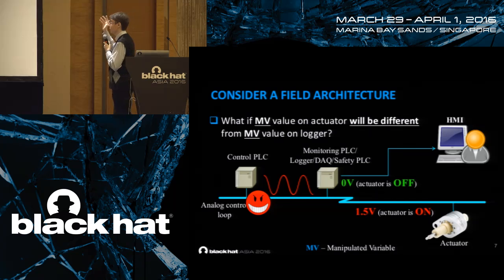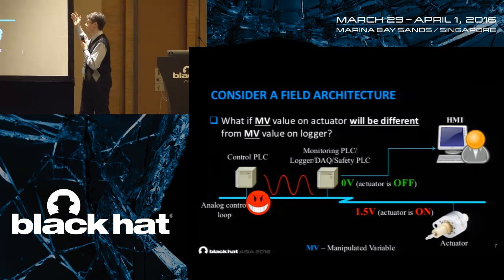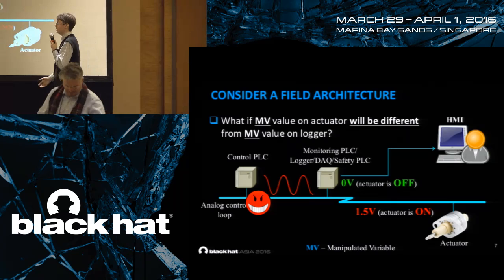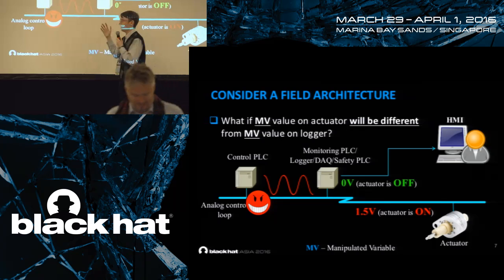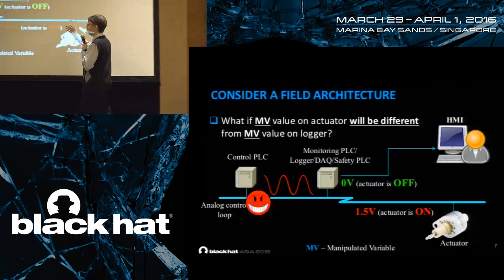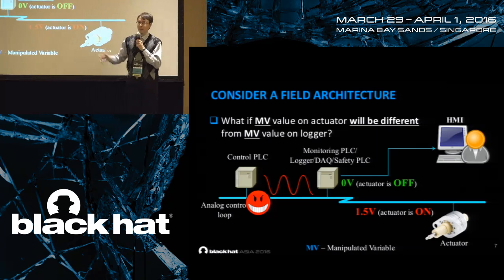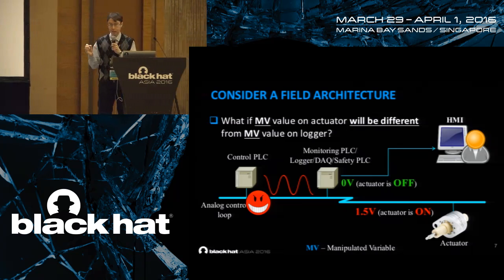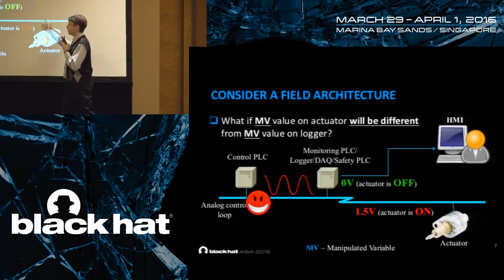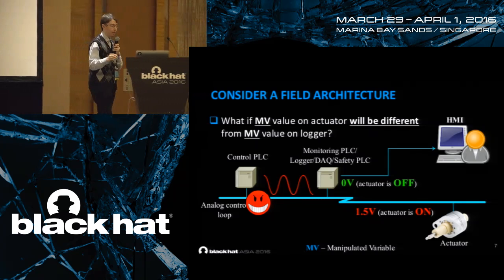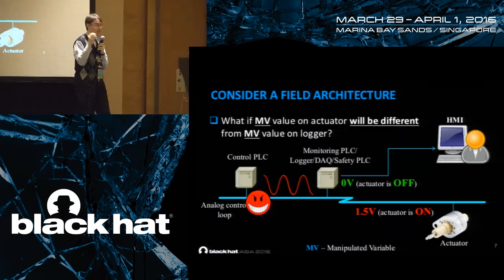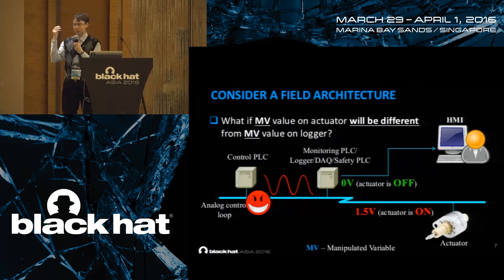Imagine such a field architecture. We have an actuator — for example, a pump or valve — controlled by some analog signal generated by a control PLC. This analog signal represents, for example, speed — some continuous analog variable. And we have a monitoring PLC which monitors the state of this variable, outputs it to the HMI system, and raises an alarm in case of a bad event. What if our manipulated variable could be understood differently at the actuator and the monitoring PLC? Is it possible to have, for example, a value of 1.5 volts here and 0 volts there on the same analog line?